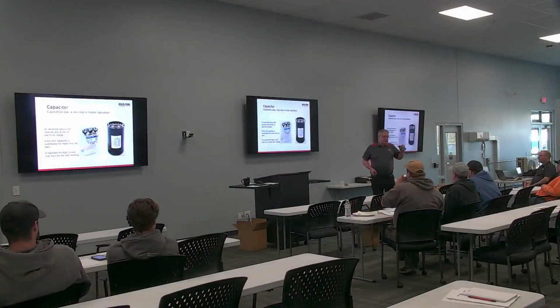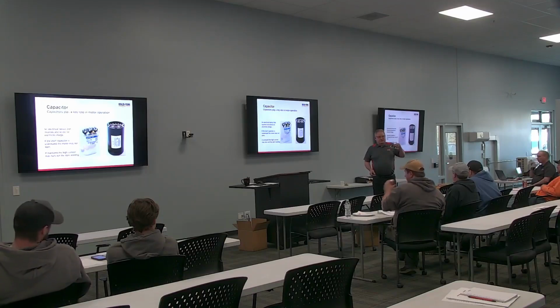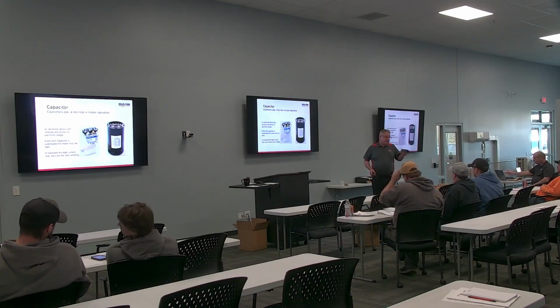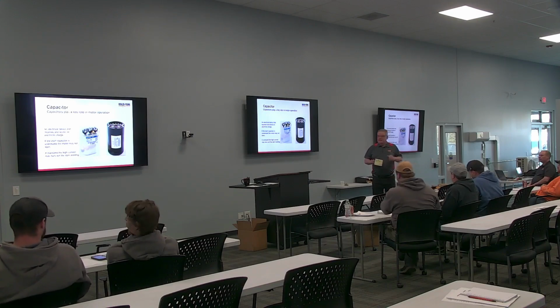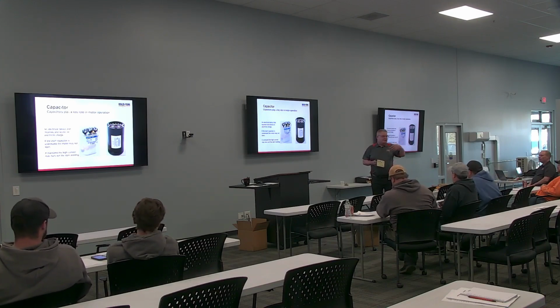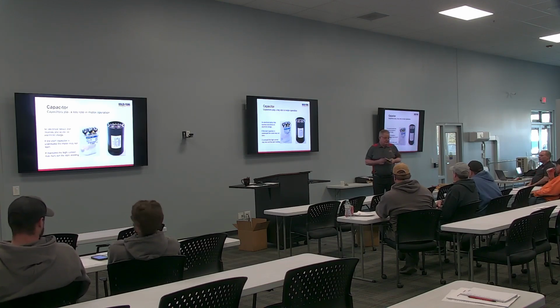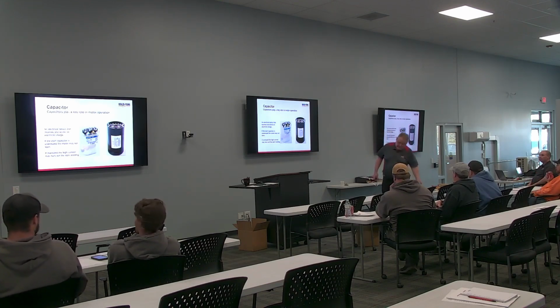The new multi-zone mini splits are going to hold the charge for almost 10 minutes because they have a new safety valve they have to shut off. So you might notice when you go to reset something, even if it connects, you shut the power off and the connect stays lit up for a little bit. There's capacitors in there and it holds that for a little bit, so it takes time to discharge.